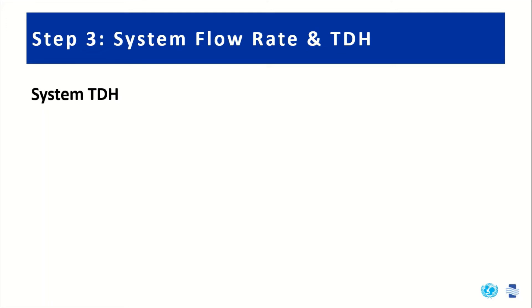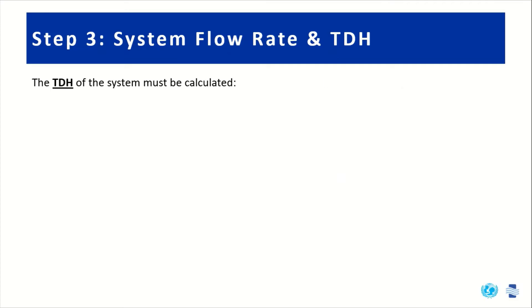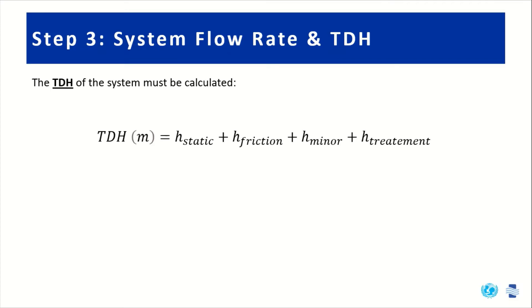Now that we've got our system flow rate, we're ready to calculate our system TDH. It's important to see the overall layout of our system: the bottom of the borehole, the pump, the dynamic water level, a well cap, then piping through treatment equipment and all the way up to the top of the water tank. The table shows the elevations of these various system components.